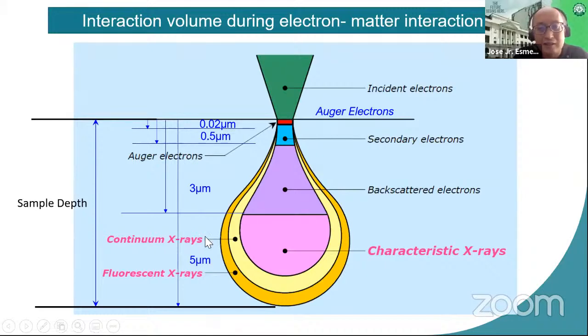Far deeper is the continuum of X-rays and fluorescence X-rays. In the much deeper region, around 5 microns, you can see the characteristic X-rays. This is where the energy dispersive X-ray spectrometer works. Because of that interaction, as the accelerated electrons with more energy penetrate the surface, they release X-rays. These X-rays are very important for identifying the elements of the material.